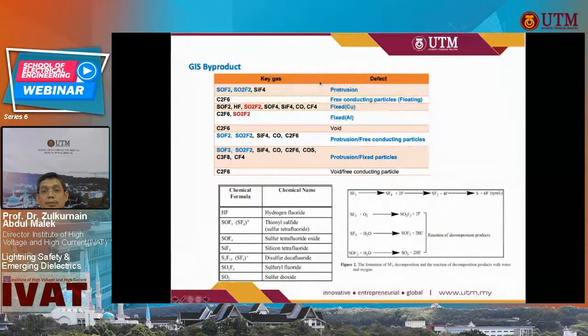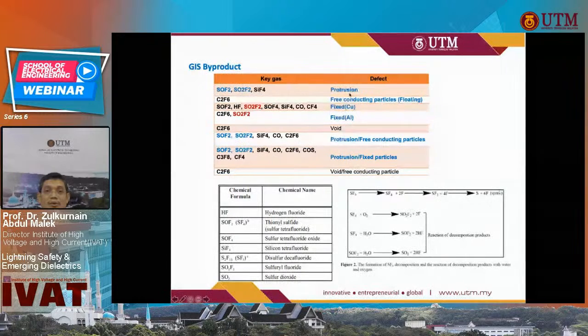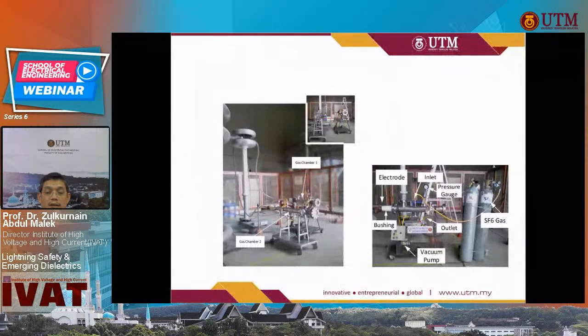And we do this in the lab and we simulate the defects that cause the partial discharge to occur inside the gas chamber. And the type of byproduct that we detect depends on the defects that we introduce. For example, SOF2, SO2F2 appear always in protrusion defects. So we can use this to diagnose the defect inside the chamber or inside the GIS by just looking at the byproduct gases. So in the lab, we have two chambers carried out in parallel and energized at about 50 kV over 5 days, and we take a sample every 1 day.